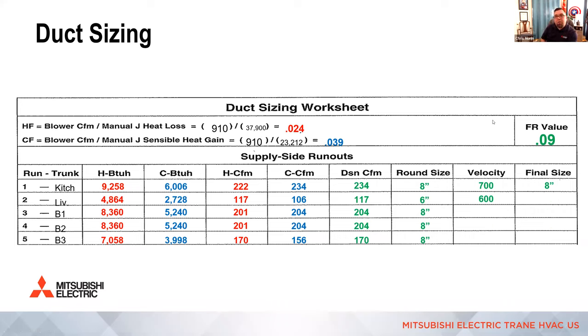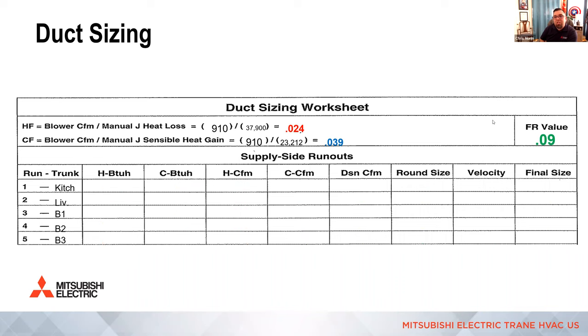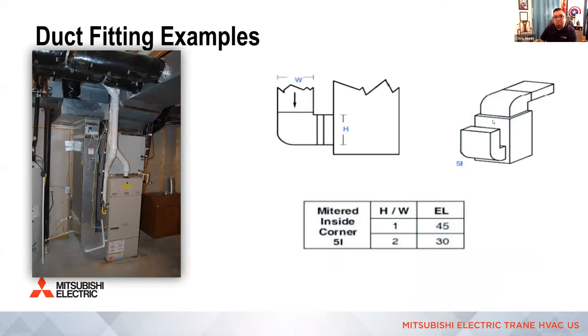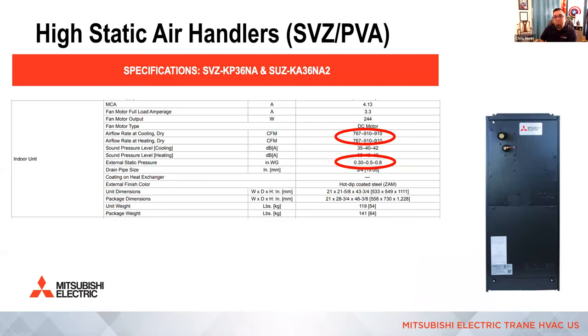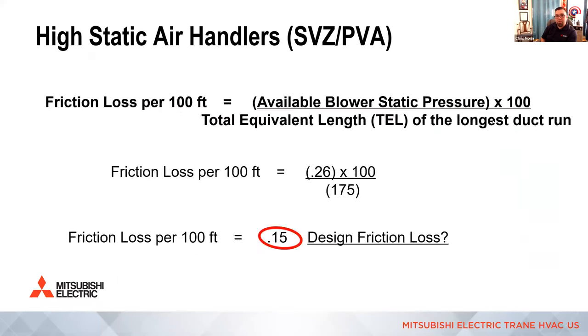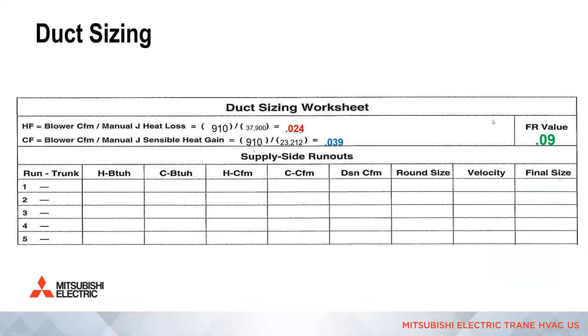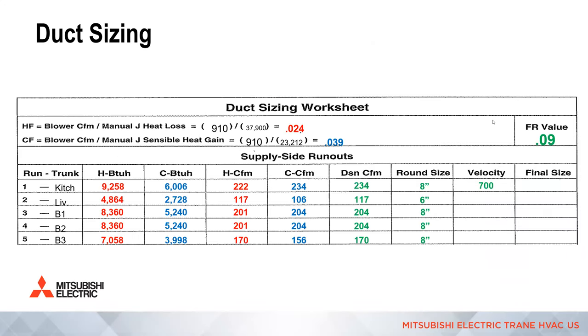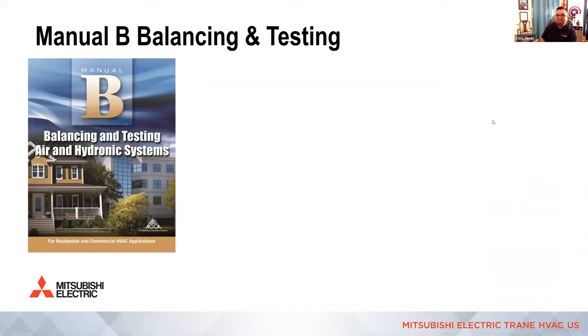Just to show you, I'm going to kick back up quite a few slides to get to the submittal for the SVZ air handler. So that comes off of your submittal. You're going to select medium speed volume of air and medium static. That was 910 CFM in this example with a wet coil and half an inch of water column for your static pressure to start with. Let me just get back to where I was. Awesome, thanks. No problem. Thanks for stopping me there.